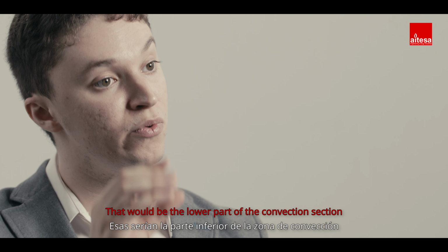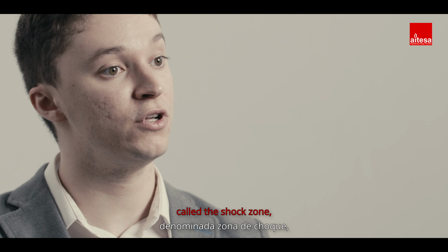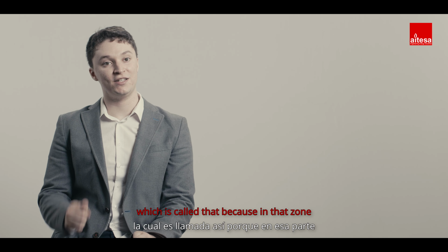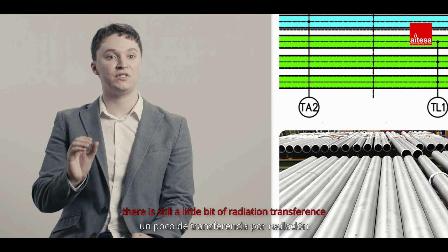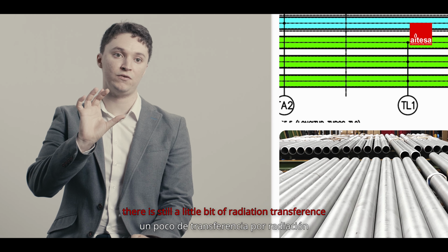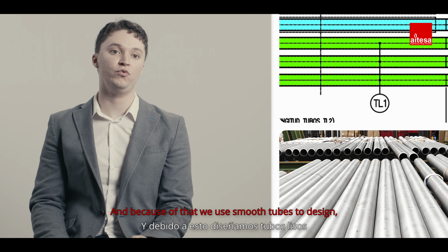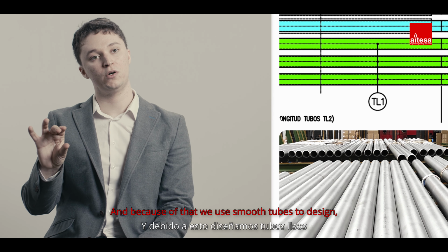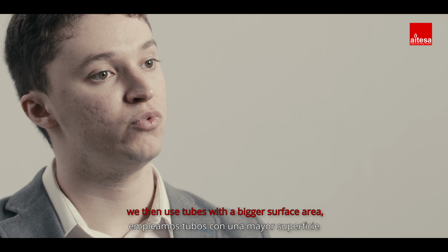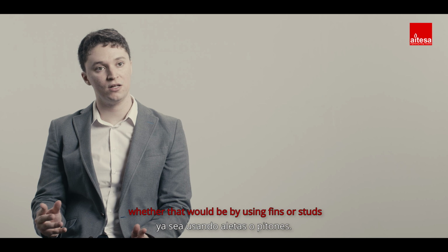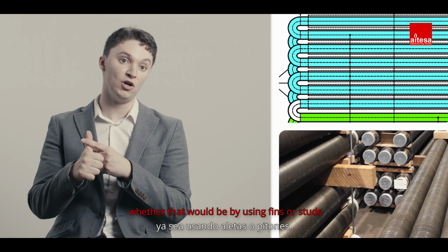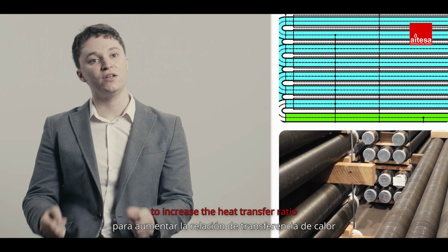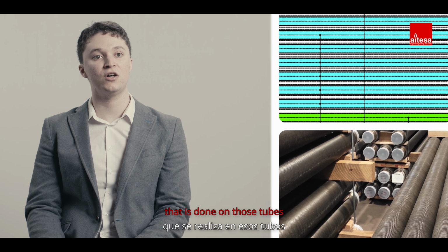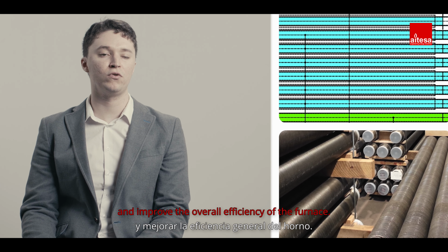That would be the lower part of the convection section, called the shock zone, which is called that because in that zone there is still a little bit of radiation transference that occurs, and because of that we use smooth tubes to protect the equipment. On the upper side of the convection zone, we then use tubes with a bigger contact surface, whether that would be by using fins or pins, to increase the heat transfer ratio that is done on those tubes and improve the overall efficiency of the furnace.